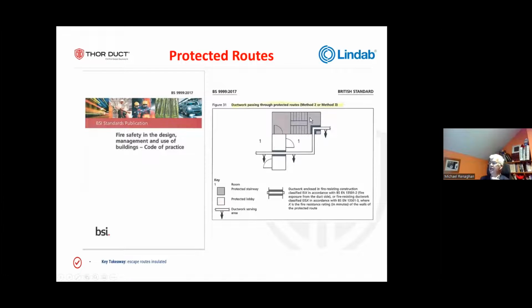Now, the reason that's insulated is because when your colleagues are going in to fight this fire, you generally take command and control in the protected areas. So you do not want a duct above your head or above your colleagues' heads that could potentially have hot gases going through it and isn't insulated. So it's insulated to protect you guys, because we're all on the way out and you guys are all on the way in. So it's very important. That's the regulation in the BS 9999 2017.